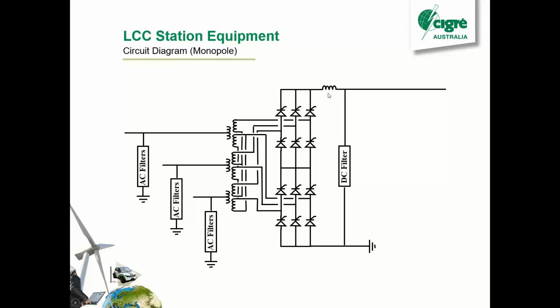So I mentioned the minimum power before. That's basically the lowest power that you can go before you get discontinuous conduction. So you really don't want to get discontinuous conduction. So the bigger your smoothing reactor is, the lower you can go before you hit your minimum power limit. So it's about 5% what we've got. So our minimum power on pole 3 is 35 megawatts on a 700 megawatt converter.